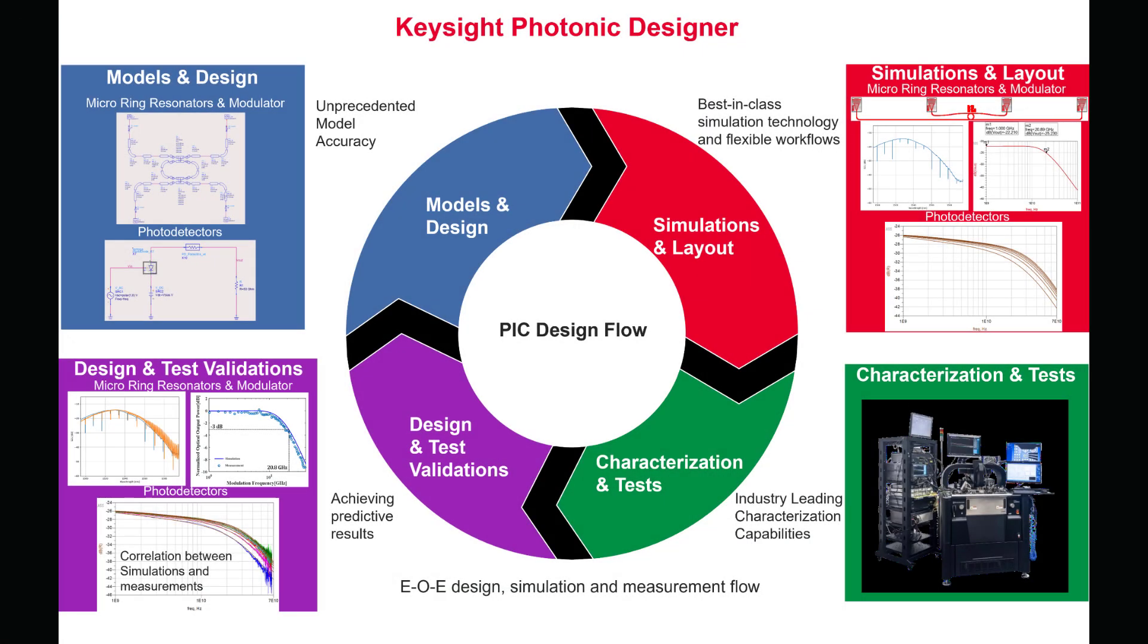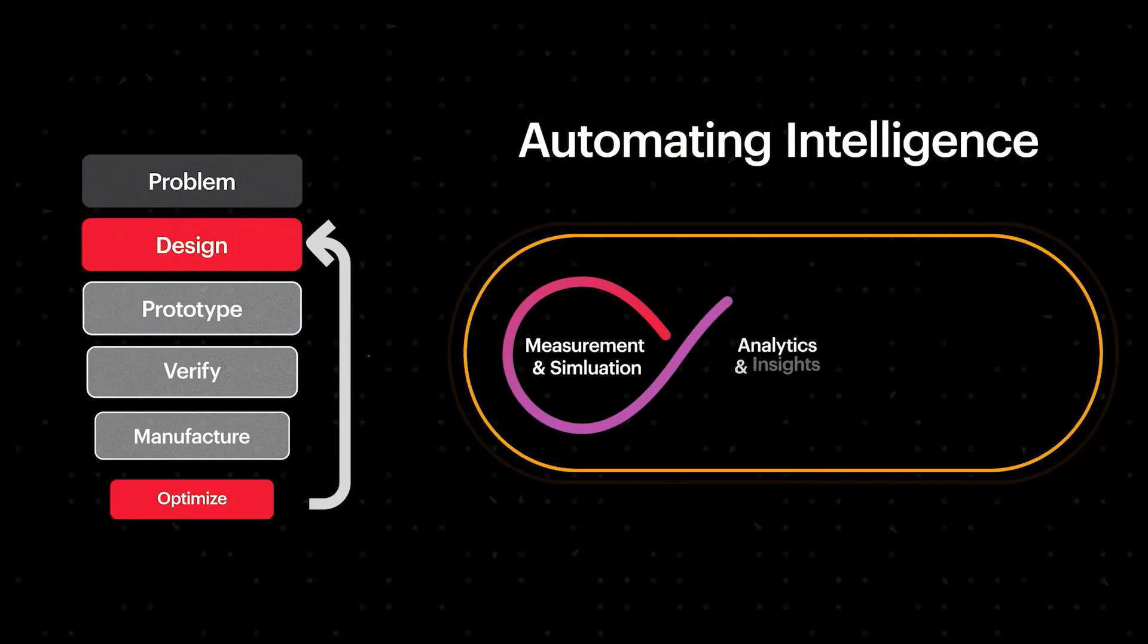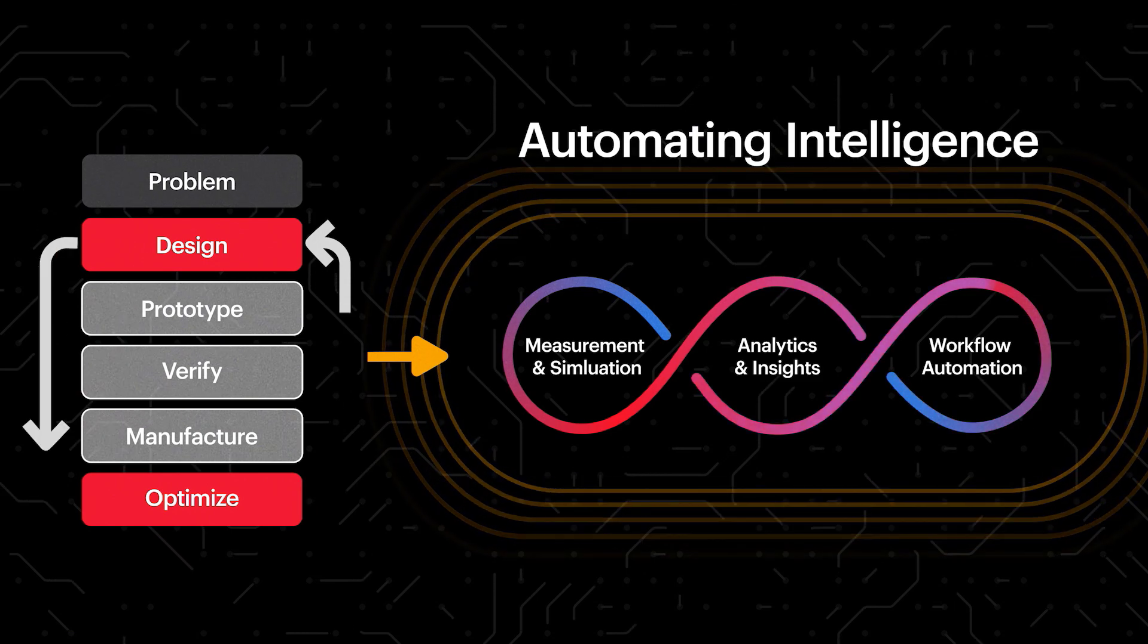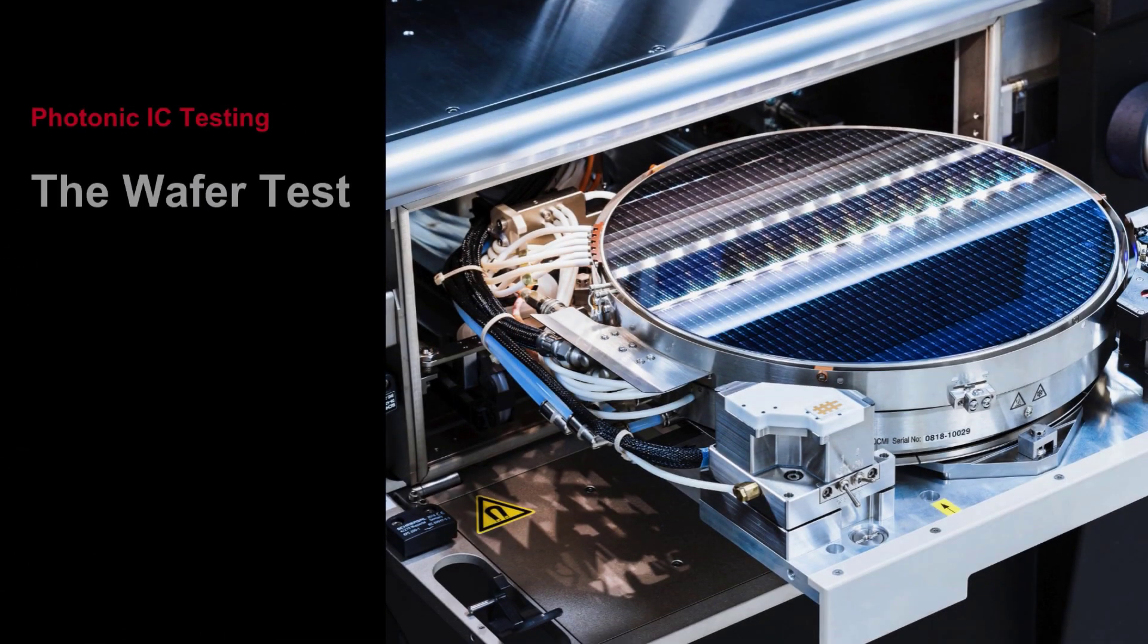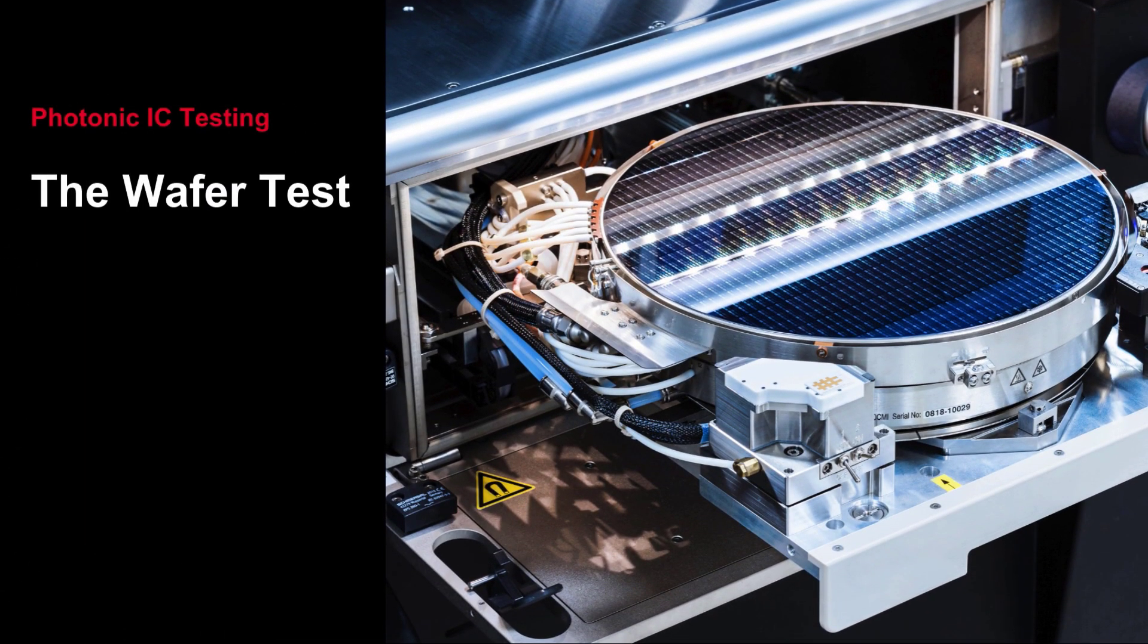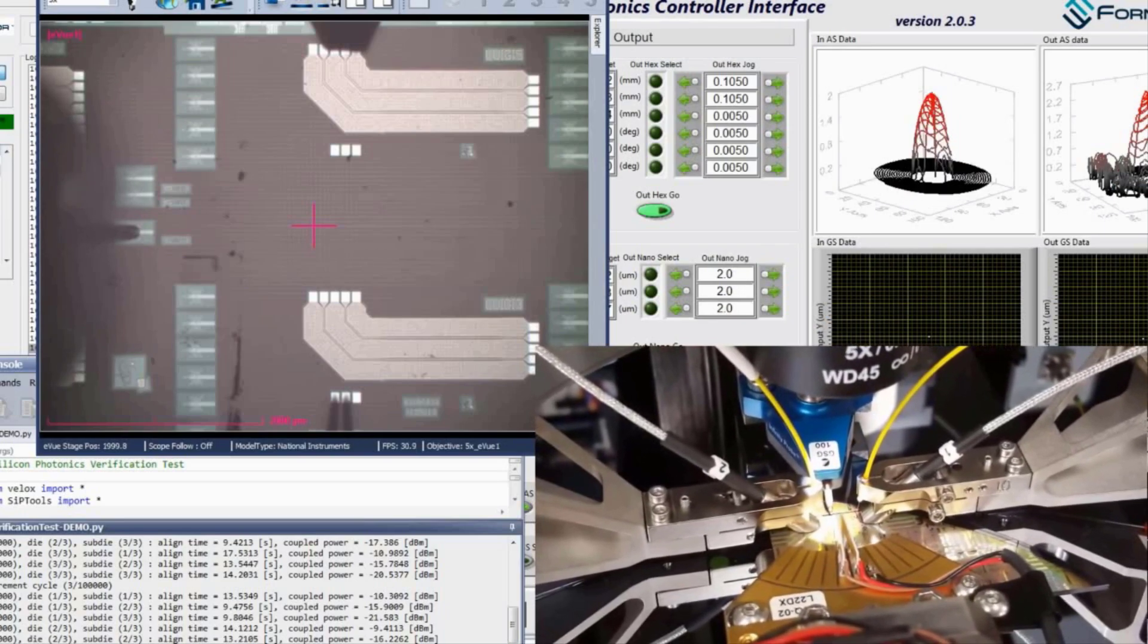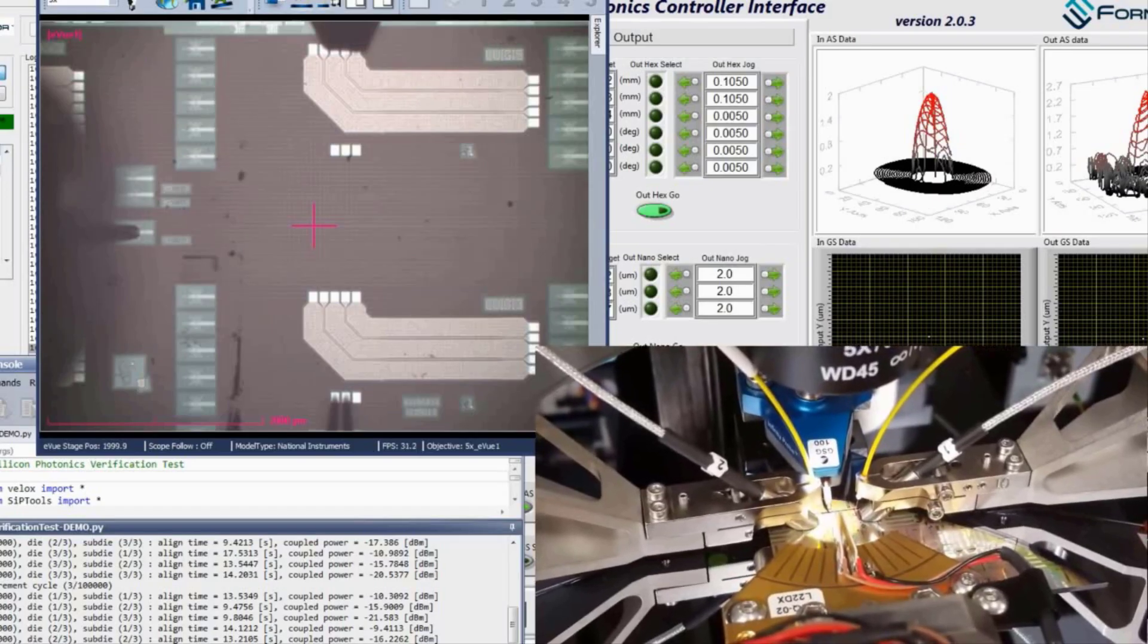These automation tools enhance test quality and significantly improve efficiency. The wafer test: the 300-millimeter wafer tester uses Keysight's PathWave Test Automation to control DC, optical, and RF probes and test each device on the wafer.